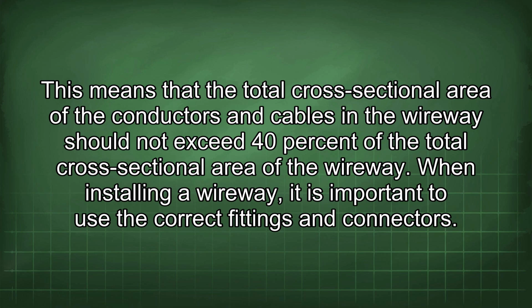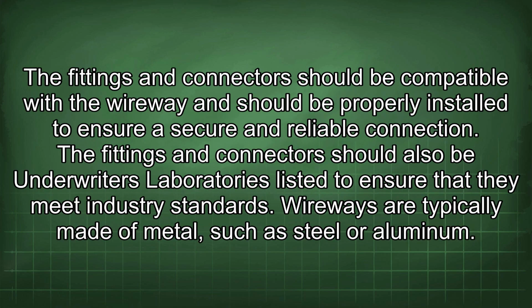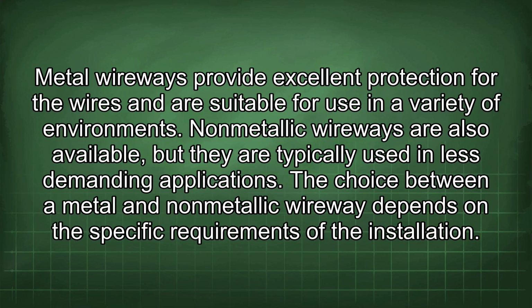When installing a wireway, it is important to use the correct fittings and connectors. The fittings and connectors should be compatible with the wireway and should be properly installed to ensure a secure and reliable connection. Fittings and connectors should also be Underwriters Laboratories listed to ensure that they meet industry standards. Wireways are typically made of metal, such as steel or aluminum. Metal wireways provide excellent protection for the wires and are suitable for use in a variety of environments. Non-metallic wireways are also available, but they are typically used in less demanding applications. The choice between a metal and non-metallic wireway depends on the specific requirements of the installation.